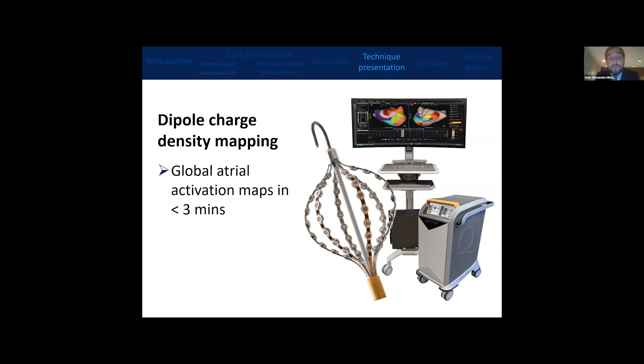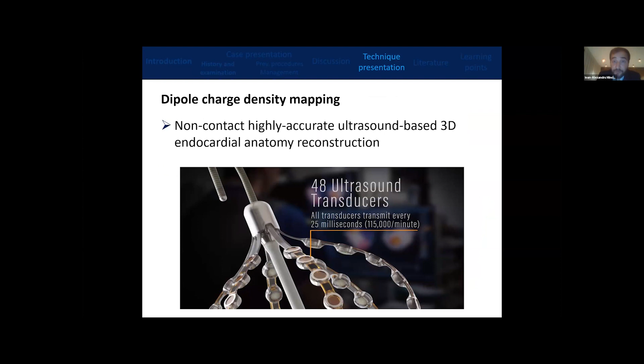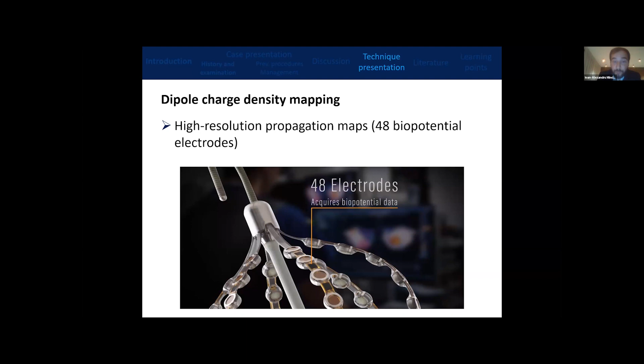And we can see here, we start mapping by putting the catheter in the middle of the atrial chamber, then doing the non-contact, highly accurate ultrasound-based 3D endocardial anatomy reconstruction using the 48 ultrasound transducers on the catheter. After we have the anatomy already reconstructed, then we create the high-resolution propagation maps with the 48 biopotential electrodes, which are placed between the transducers.